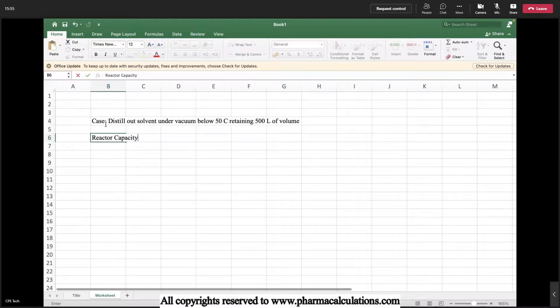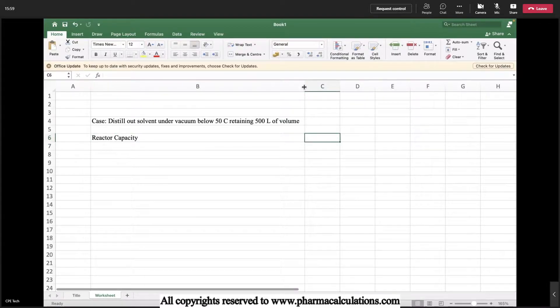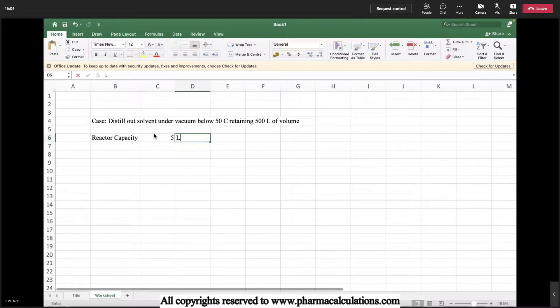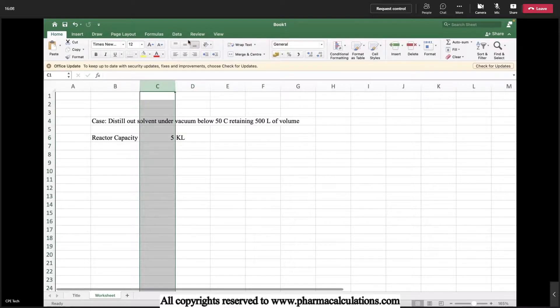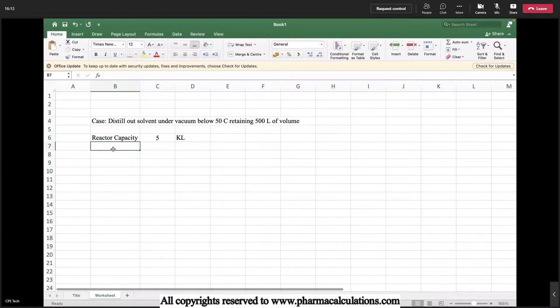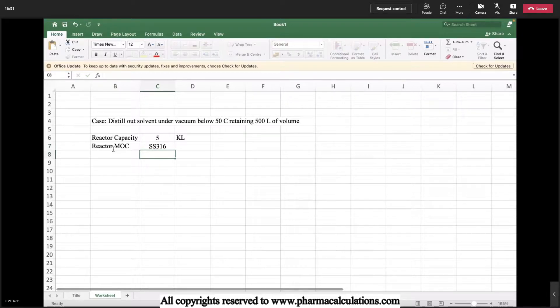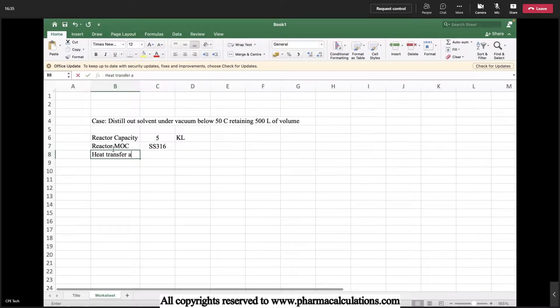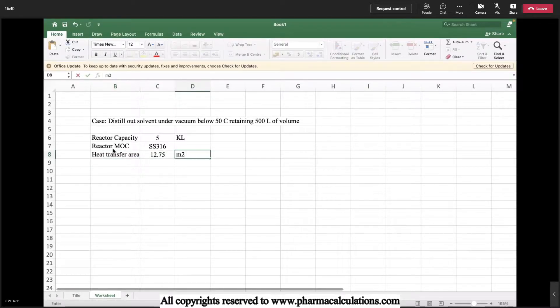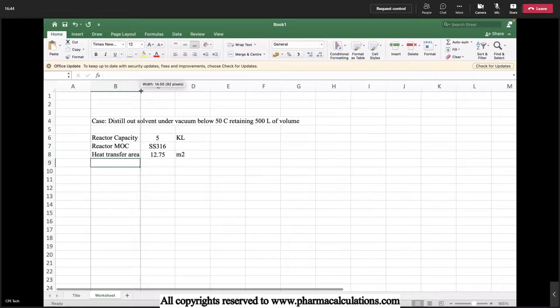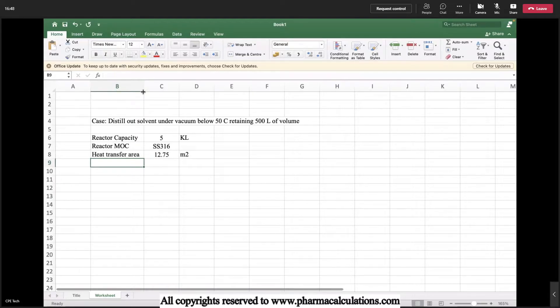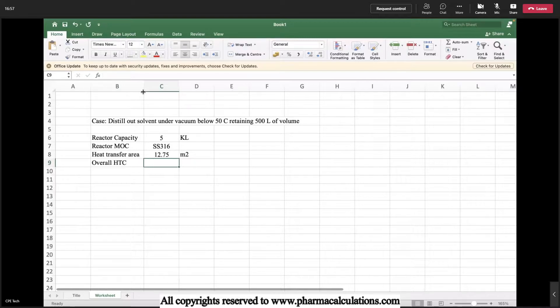The reactor capacity is 5 KL. Today I am going to deliver two types of methods: the first is a simpler theoretical approach, and the second is the more accurate actual method. The reactor material of construction is SS316, and the heat transfer area is taken from the GA drawings or estimated using theoretical calculations shown in the last video. The overall heat transfer coefficient for this SS316 reactor is considered as 250 kilocalories per hour per meter squared per degree centigrade.